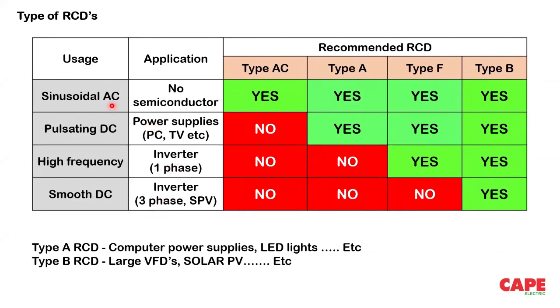Say, for example, if the usage is completely sinusoidal, that means there are no semiconductor devices, you can use a type AC. Any of these 4 types of RCDs can be used. There are 4 types: type AC, type A, type F, and type B. All the 4 can be used. If you have a pulsating DC load, such as power supplies of computers, power supplies of television, and nowadays all these modern electronic devices, then leakage in the pulsating DC can also create a shock. And for that particular purpose, you have to use a type A RCD.